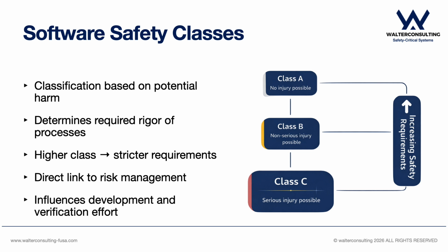How does software safety actually get classified? IEC 62304 defines 3 safety classes. But here is the key question. What determines which class applies? The classification is based on potential harm. Class A means no injury is possible. Class B means non-serious injury could occur. And Class C means serious injury is possible. Now think about this. Should all software be treated the same way? Of course not. The higher the risk, the stricter the requirements. This affects development, verification, and documentation. And this is where IEC 62304 connects directly to risk management.